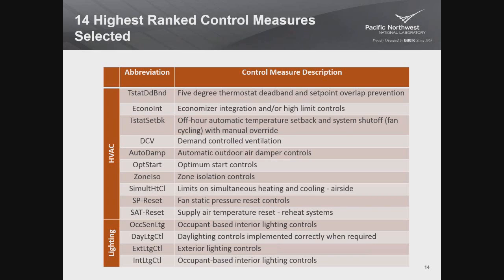The next several have to do with typically variable air volume reheat systems. The first one is the limit on simultaneous heating and cooling. Those of you who might not know the way a VAV reheat system works is that you have an air handler that provides cool air out of the air handler, very typical values, 55 degrees. It's sent out to different zones, and depending on what the demand for heating or cooling is in those zones, if the zone needs cooling, it just supplies 55-degree air, and it varies the amount of 55-degree air. If a zone is in heating, it reheats that 55-degree air. So obviously that could be a wasteful strategy. So this requirement says that before you reheat any of that air to zones that need heating, you have to reduce the airflow as low as possible and still meet the load. That's what this requirement is about.